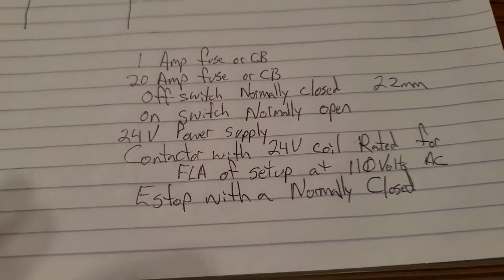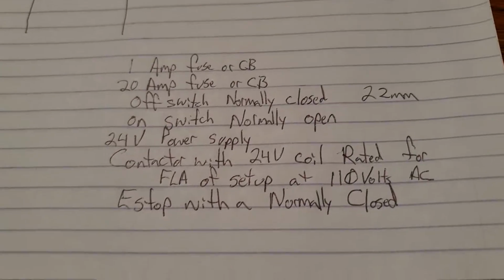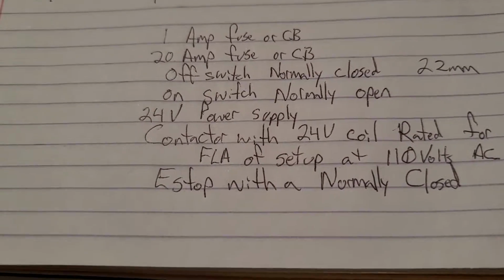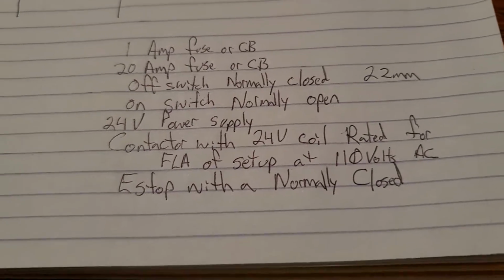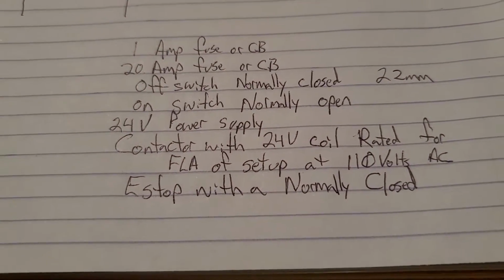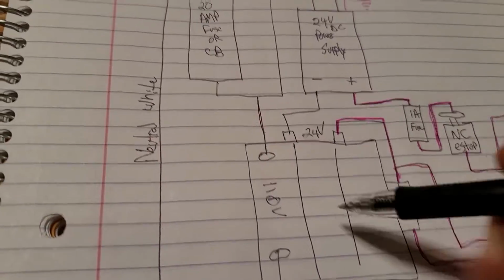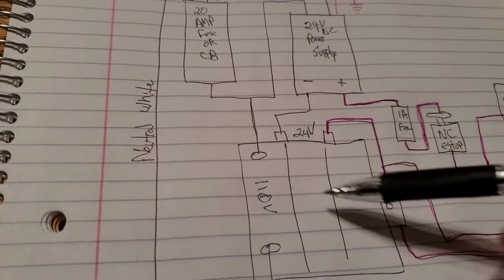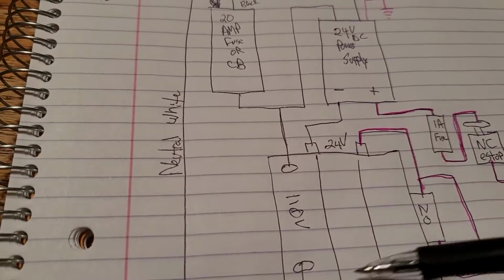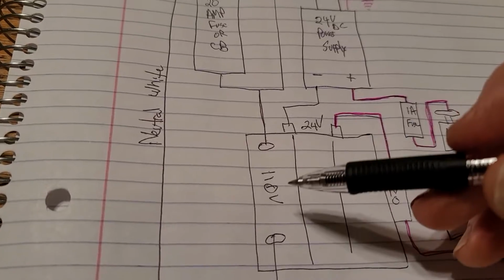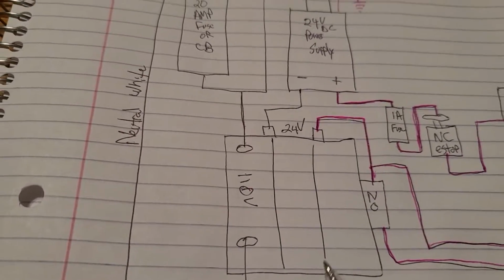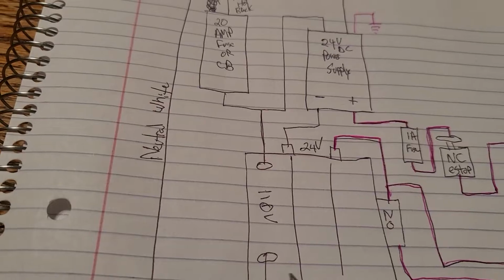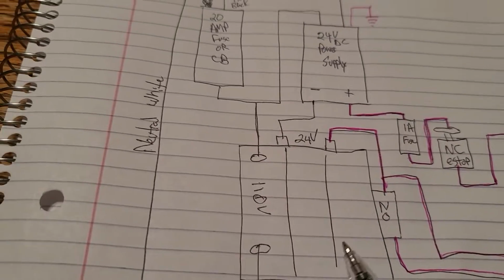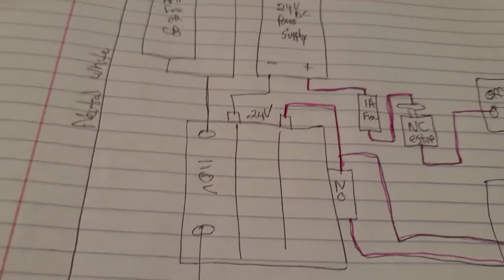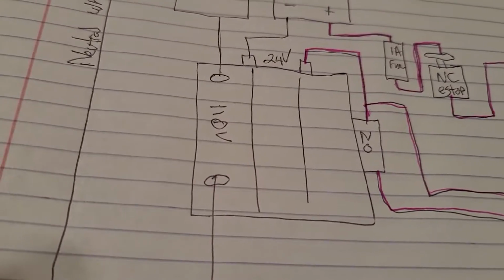So they're usually sold in series. So maybe you'll buy a series 22 contactor. And it'll have a rating on what it's rated at. Typically, most contactors, that's what this box is here. They usually have 3 connectors because almost every contactor is built for 3-phase. But in our case, we're only going to use 1. But my point is that they rate them typically at 230 volt or 460 volt 3-phase. And so you need to make sure you're looking at the single phase rating.